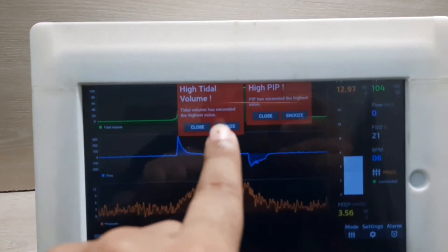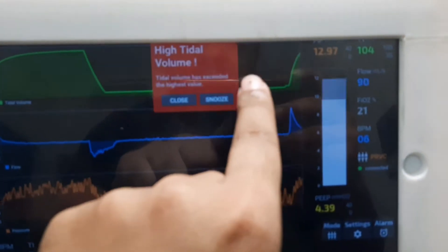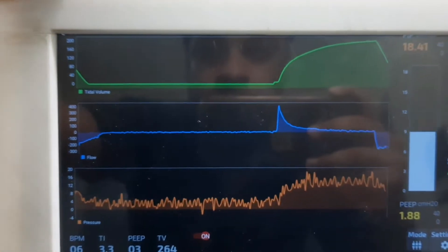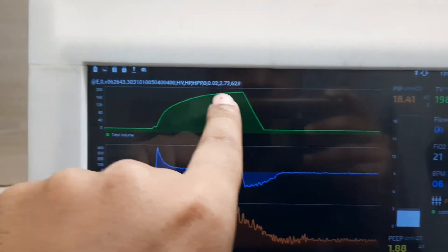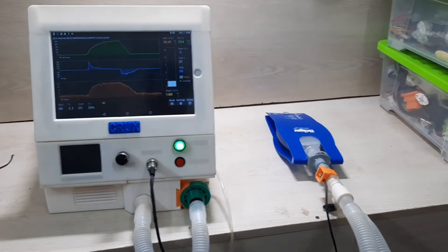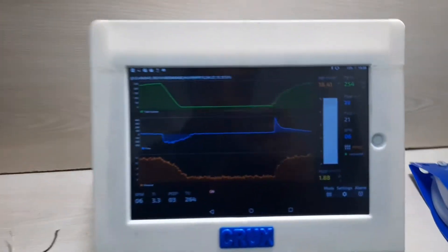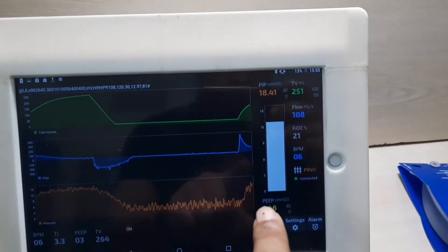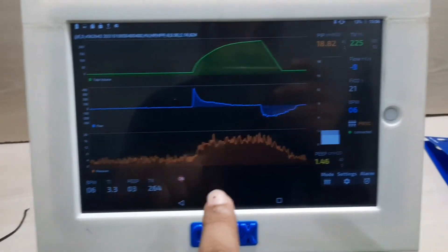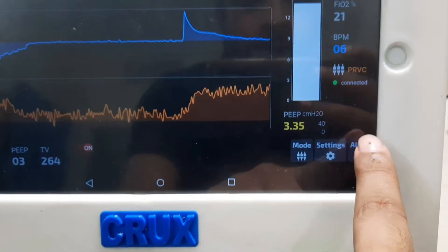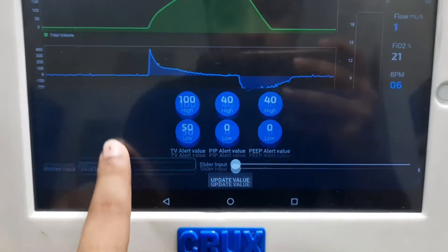Now here you can see the various alarms. So for now I will snooze all — from settings, here I can snooze everything. And here you can see the debug data that is being transferred from the internal Arduino Mega. Here you can see the ventilator is ventilating very, very well with a very nice curve. Here is the flow, here is the tidal volume, and here is the pressure, and here is the PEEP, here is the PIP, PEEP, actual tidal volume, and given tidal volume, and various other things. Here you can see the alarm has begun — if we want to change the alarm, then here we can change the alarm parameters — very easy user interface.